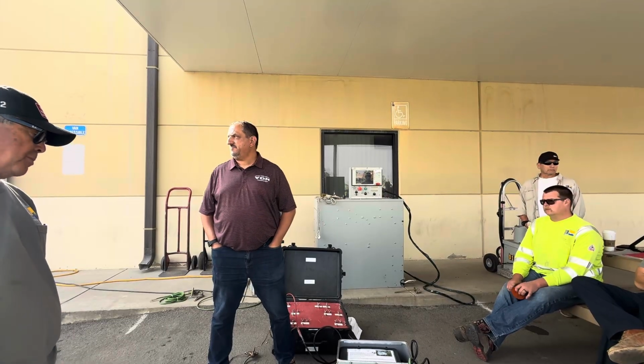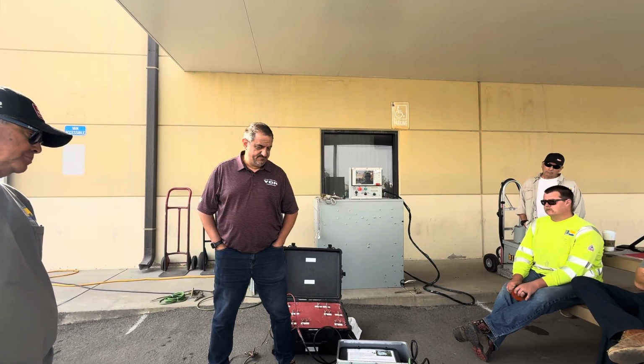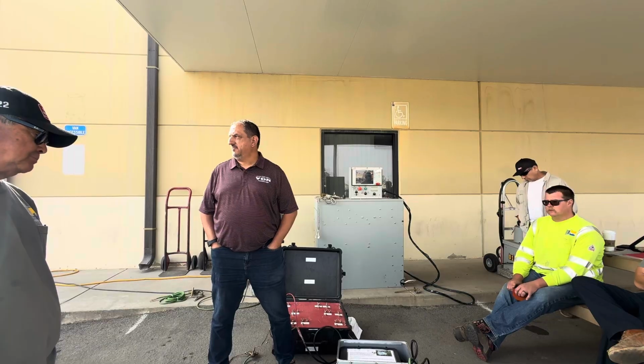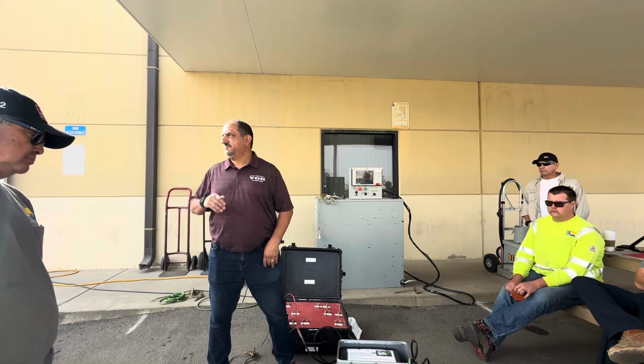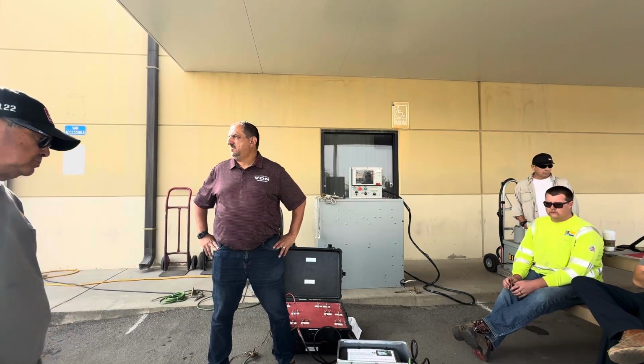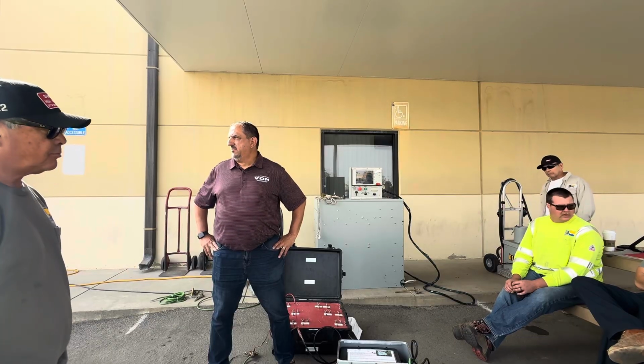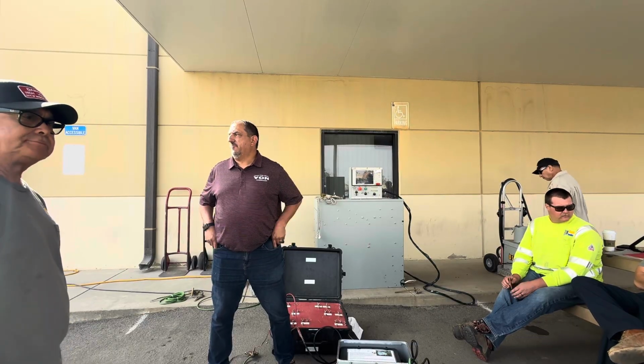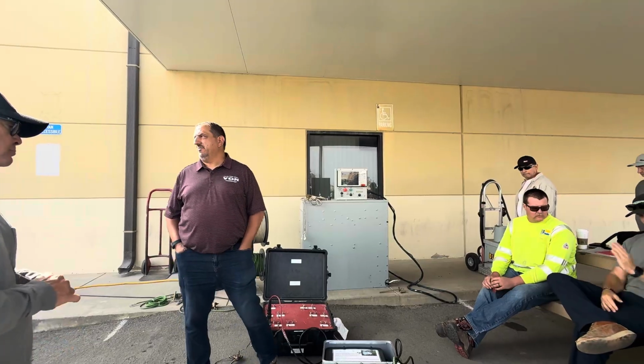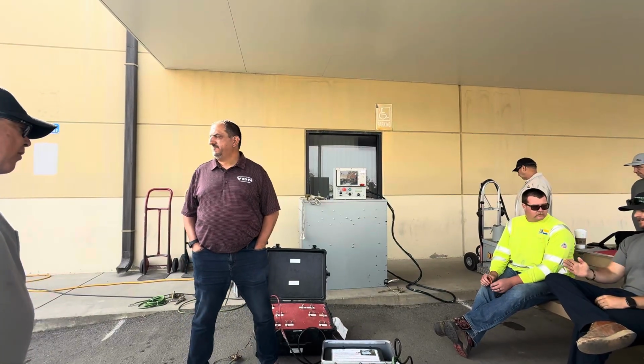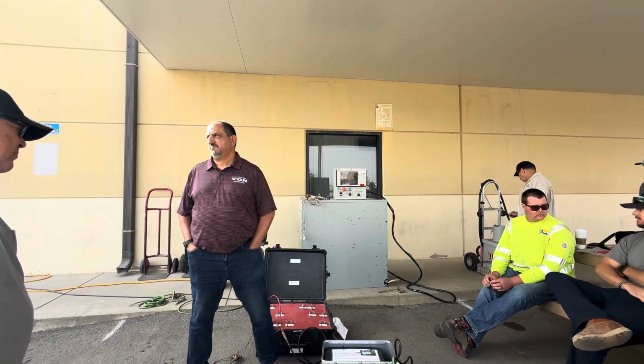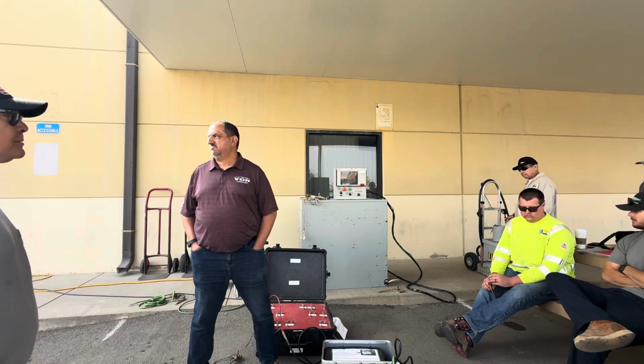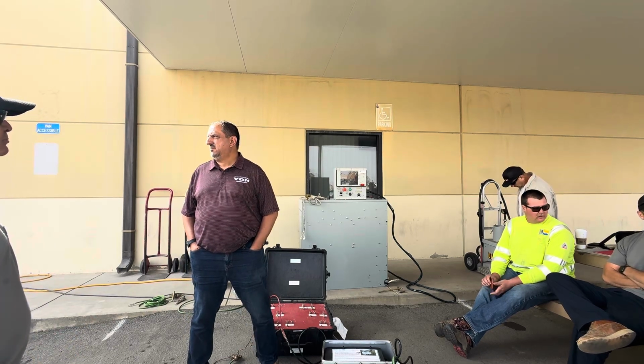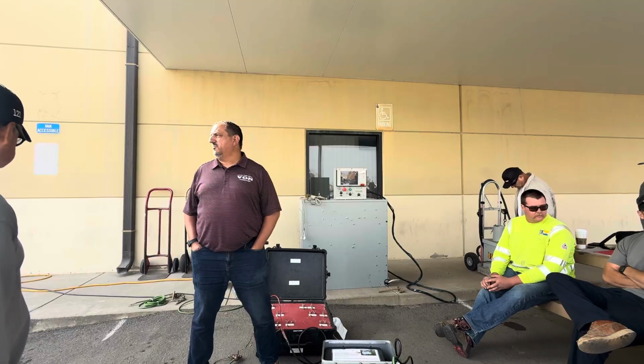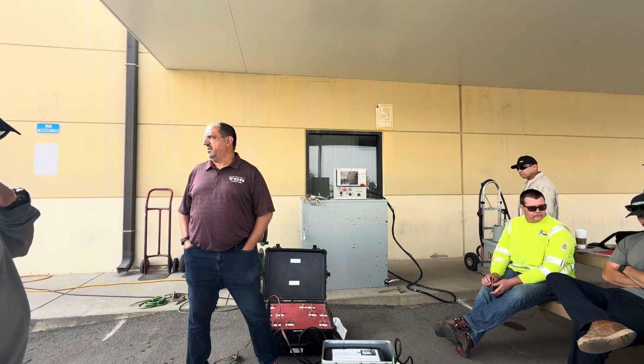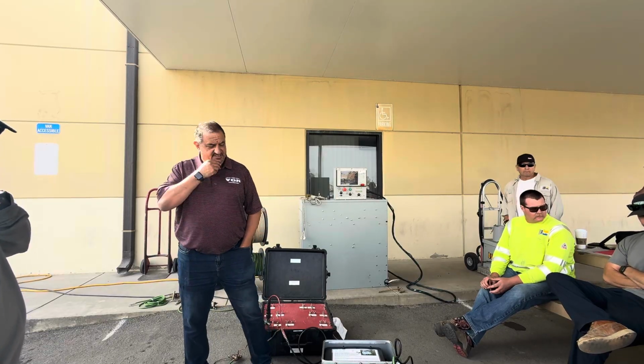It's not good to thump the transformer. Right, you're trying to find the fault, isolate the cable, and then do your thump method. But say someone is tired in the middle of the night and just thumping something, is it going to damage the transformer? No, it's not, same with the big one. Even if they went to full max, it's probably going to go to fault rather than mess with the transformer. Obviously things can happen since electricity will work, so there's always that possibility, but we're not aware of anything coming across like that.